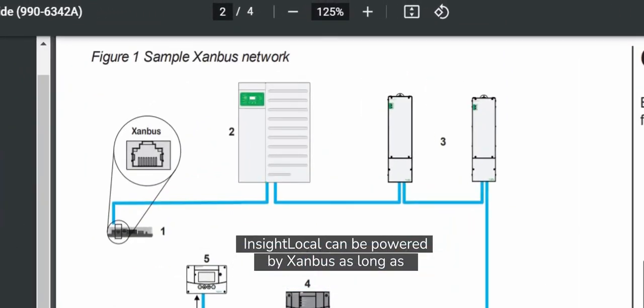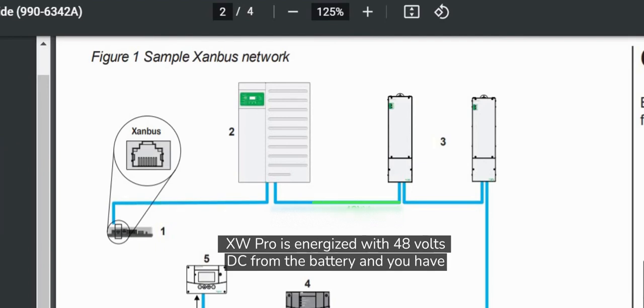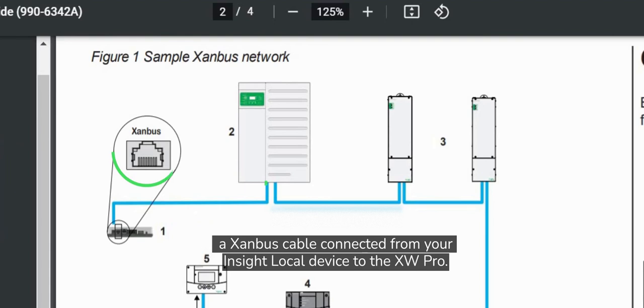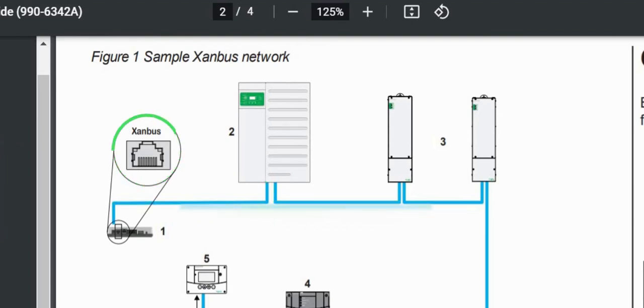InSight Local can be powered by Xanbus as long as XW Pro is energized with 48 volts DC from the battery and you have a Xanbus cable connected from your InSight Local device to the XW Pro.